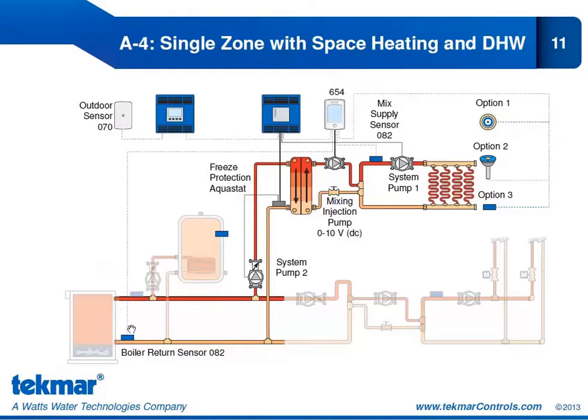Another thing I want to draw your attention to is here we have our boiler return sensor. So in this application we want to do boiler protection. So we have a boiler return sensor, and that's going to be connected to the 654. Now if you remember, on the terminal strip there is a shared terminal between the boiler return and outdoor sensor. So because we're connecting this boiler return sensor to the 654, it means we cannot connect an outdoor sensor directly to the 654. But because we're connected to a house control, we can connect an outdoor sensor to the house control, and that information is communicated through tekmarNet to the 654.